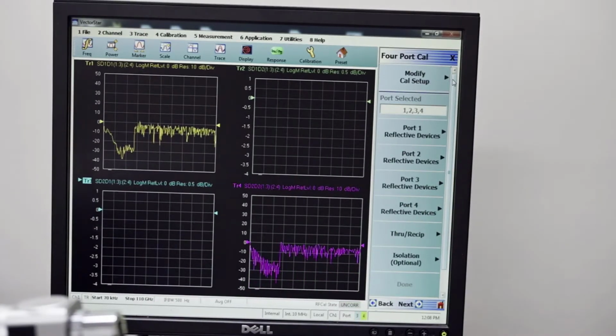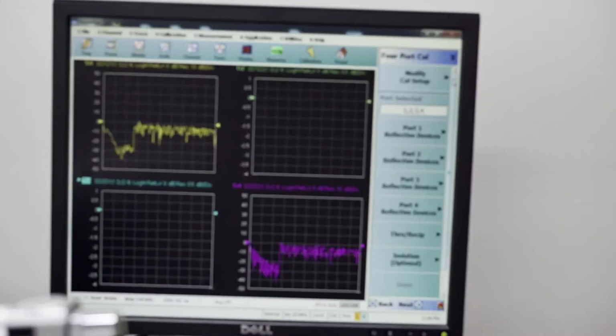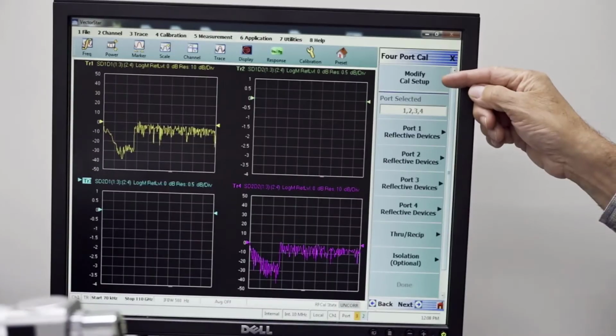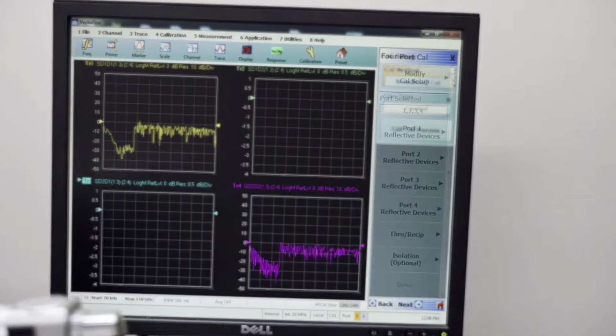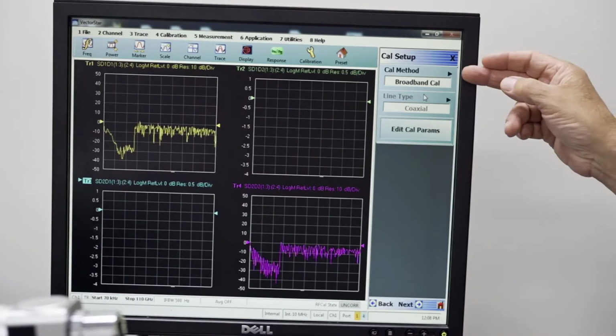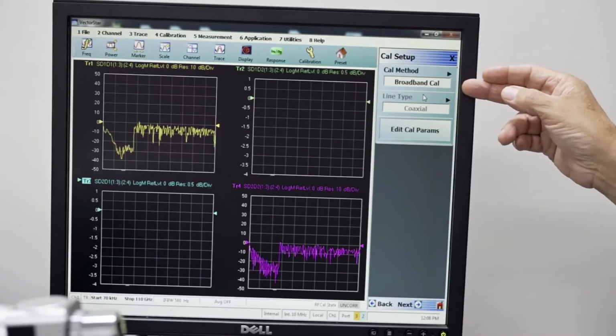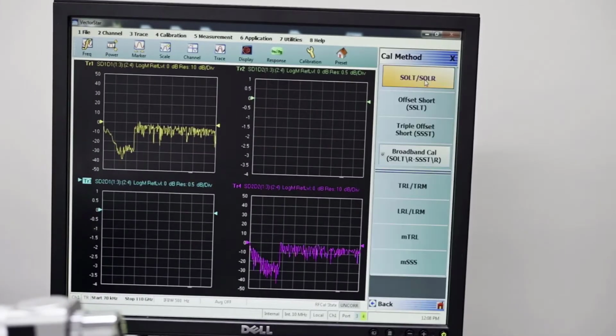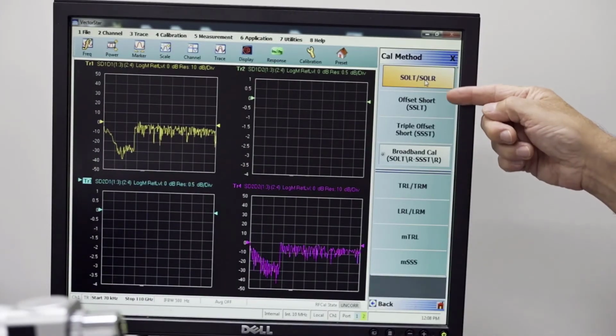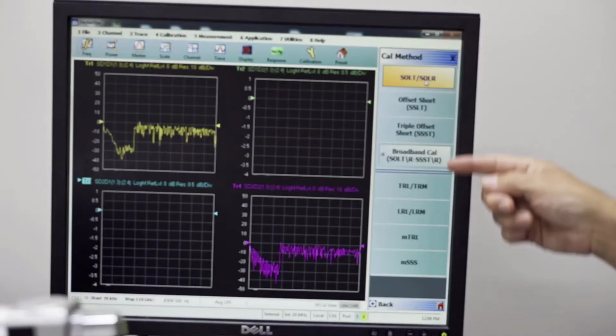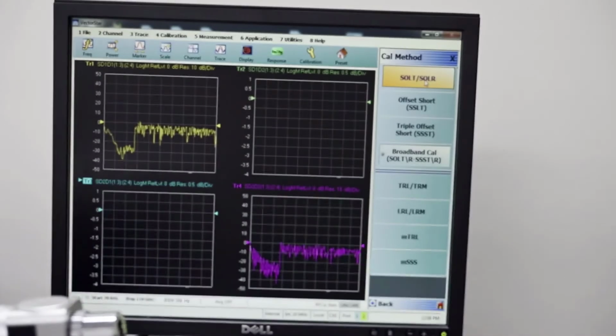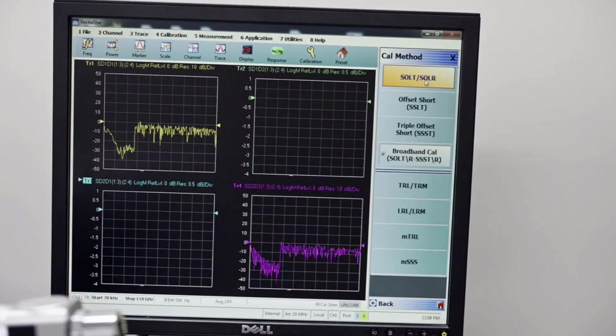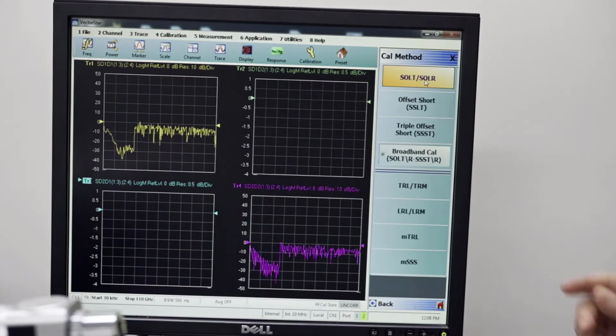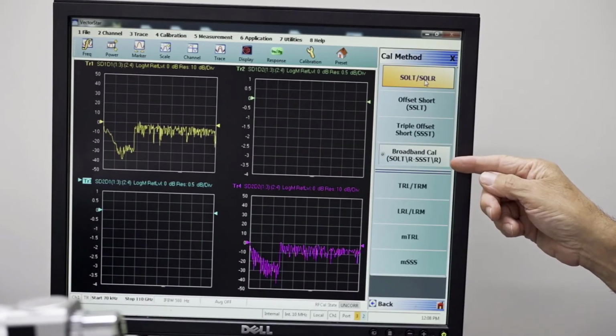In order to show you how we configure the system and set it up properly for our calibration, we'll go to the modify cal setup. And then you see that we have our cal method selection first. And this gives us the opportunity to designate the type of calibration we want to do. And so there's a wide range of choices. For this coaxial calibration, we're going to select the broadband cal.